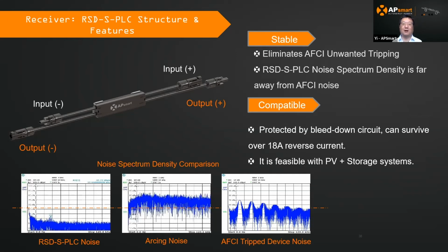On the right side, we picked some failed devices. If you look carefully, you can see their spectrum density actually interferes with the arcing noise, which is the root cause of the AFCI unwanted tripping issue.